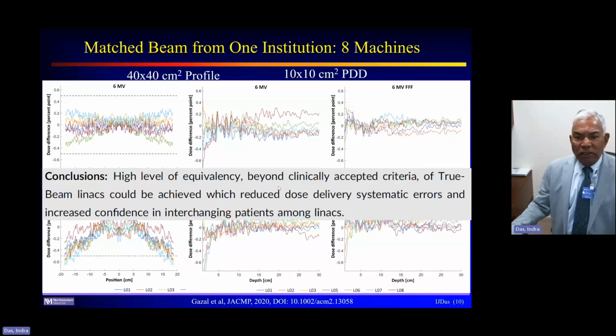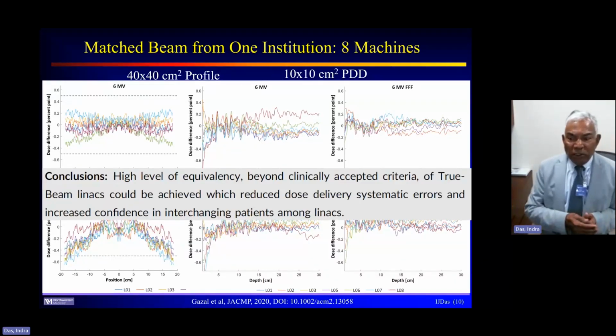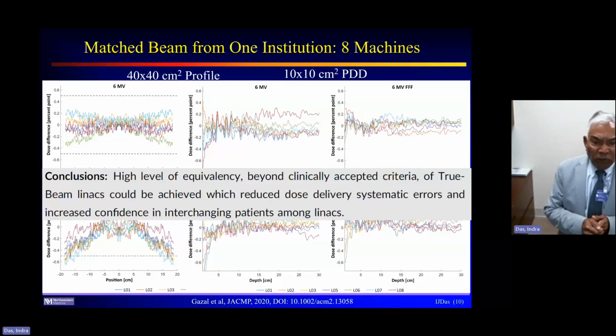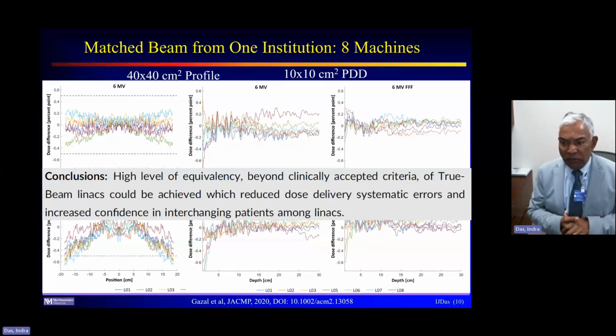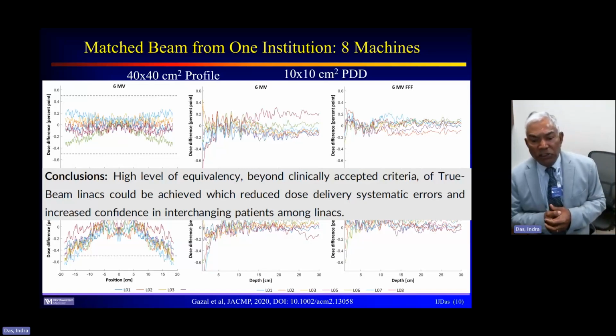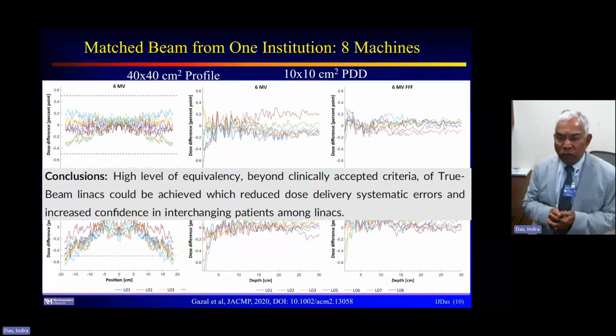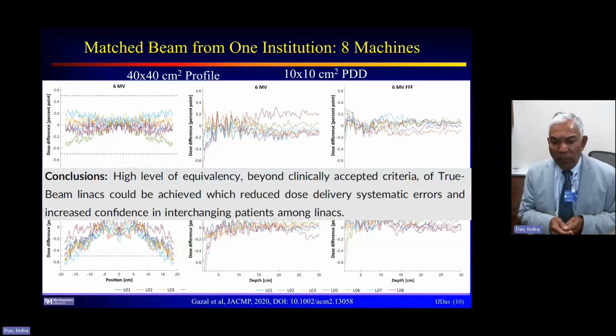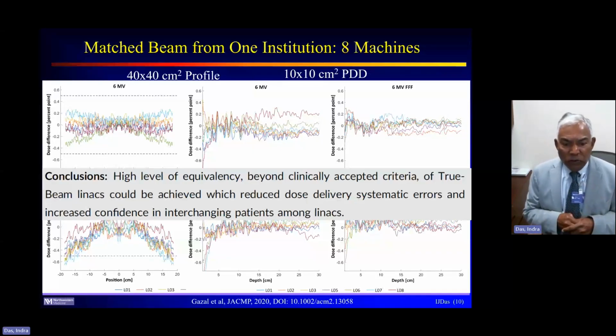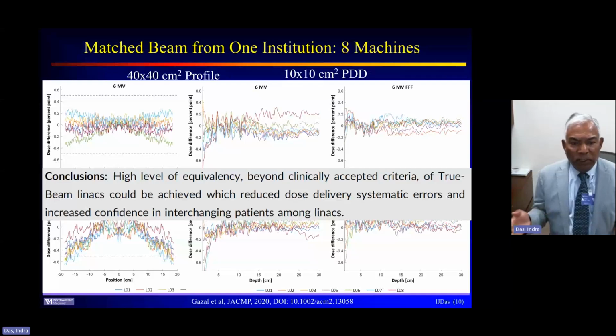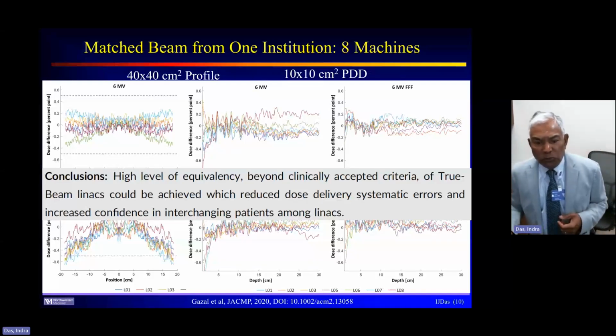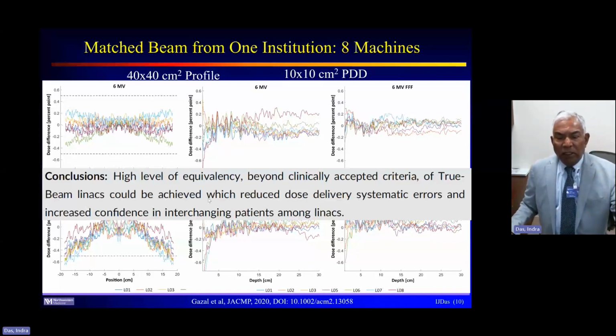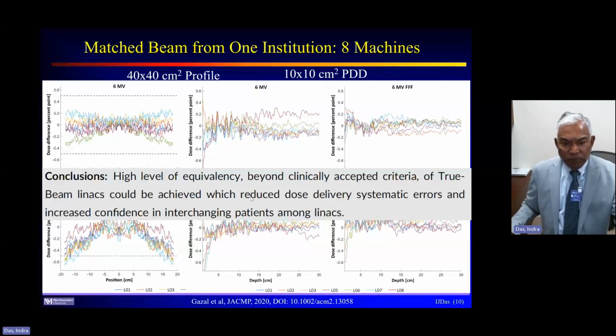So the question is, what to do? Well, this paper concludes that a high level of equivalency beyond clinically acceptable criteria for TrueBeam Linacs could be achieved, which reduces dose delivery systematic errors and increases confidence in interchanging patients among Linacs. So if you have more than one TrueBeam in the department, and if you are diligent, you could move the patient from one to the other because it's just going to be within 0.2% or 0.5%. That's what the data indicates.